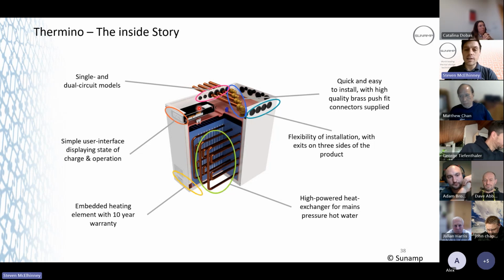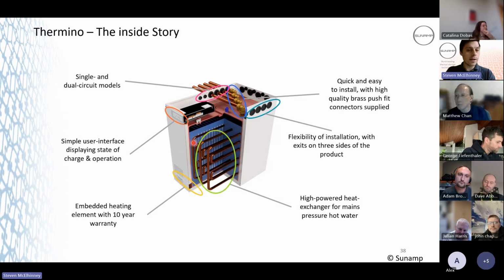The reason for that is a Thermino E is charging bottom to top, but it's discharging top to bottom. So water comes in at the top, all the way to the bottom, and then it comes out. They've figured out that's the best way for the E to work when it's discharging its temperature, and a lot of it's to do with set points as well, which I'll cover. That phase changing material is fully up to temperature here, and that cold water is essentially being preheated as it goes down. If you were to look at the 3 temperature sensors, that top sensor is the first one to lose its temperature, and then it will start to preheat.